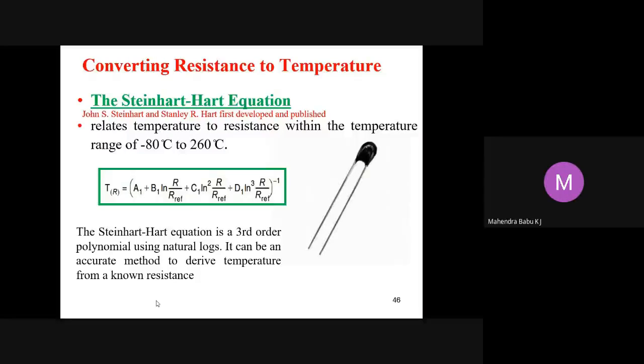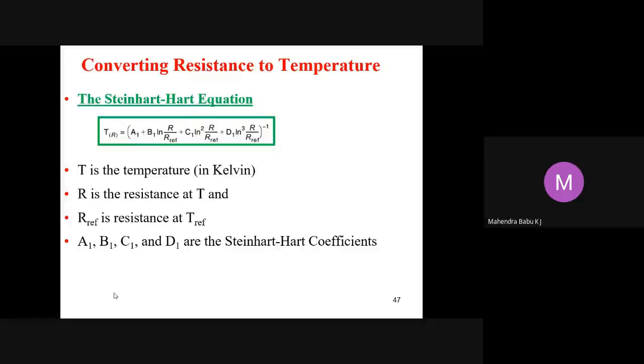This is a third order polynomial using natural log, and it can be an accurate method to derive the temperature from a known resistance. In this equation, T is the temperature in Kelvin, R is the resistance at a temperature T, and R reference is the reference resistance at the reference temperature. A1, B1, C1, D1 are the Steinhart-Hart coefficients.